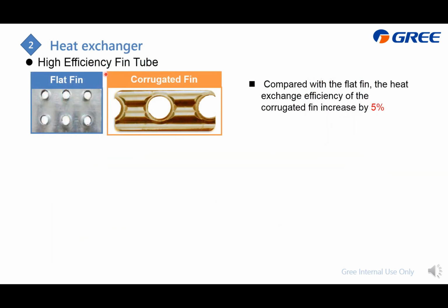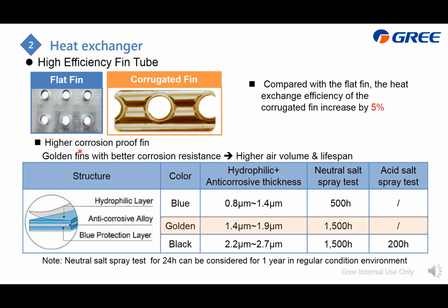Heat exchanger. First is the fin. The fin is a corrugated fin, which means the surface is not flat. And what we can get is we can make it into a structure like this. First, it raises the heat transfer efficiency. Next, during defrost, the ice does not stick to the fin easily, which means if it becomes water in defrost, it will flow out easily. As for the anti-corrosion, it belongs to the golden. And actually in our design system, we divide the anti-corrosion level by colors: blue, golden, and black.